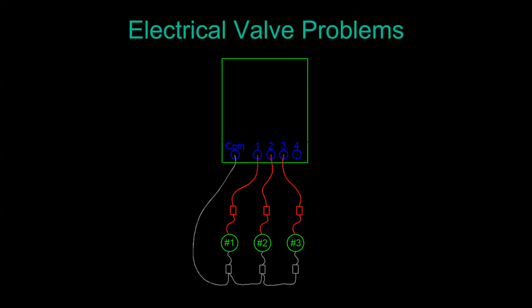This is AC volts, not DC, so you don't have a ground wire or anything like that. So you've got your individual terminals for your stations, 1, 2, 3, 4. Each valve, that solenoid has 2 wires. So one wire for valve number 1 is connected to terminal 1, same with 2, same with 3. Then you've got this other terminal over here marked C, COM, or common.